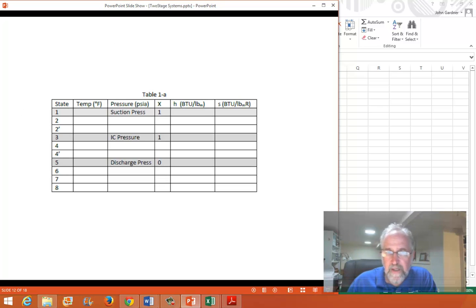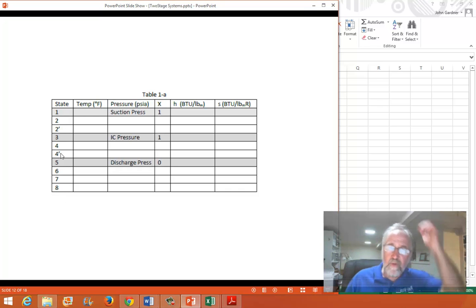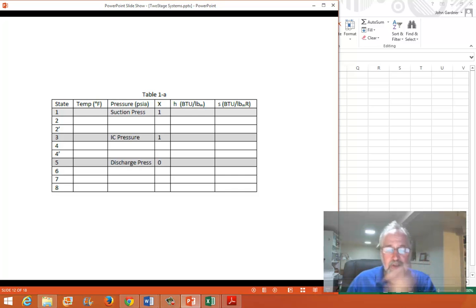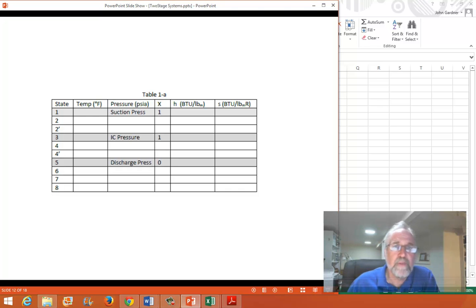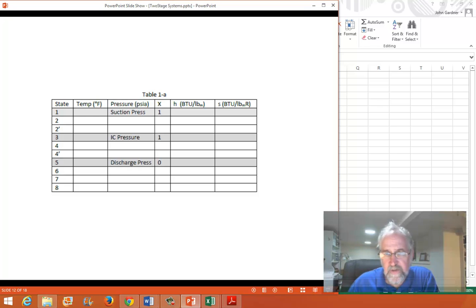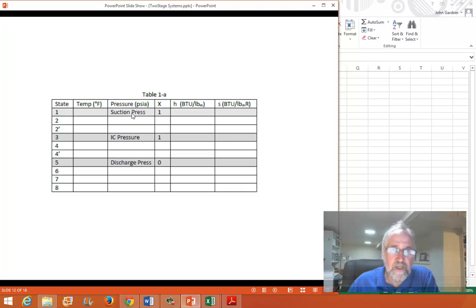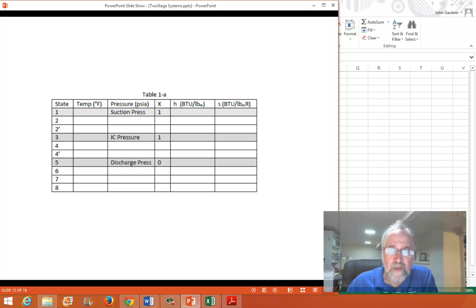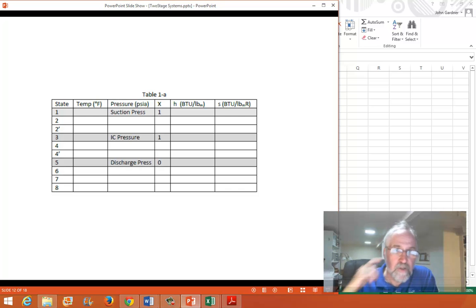Here's the table. We see the eight states and these two prime states — two prime and four prime — which are the outlet states of the two compressors, but I'm relaxing the isentropic condition. There's a little shading on these three: we assume we know the suction pressures of the two stages, which is the intercooler pressure, the actual low-end suction pressure, and the discharge pressure of the second stage. These are usually set by the controllers and operators of the system.